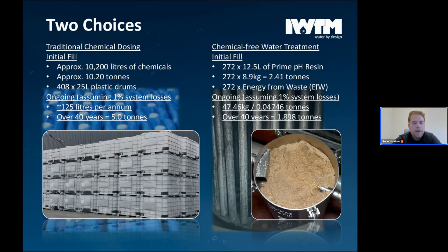And if you didn't know what chemical-free water treatment is, it maintains and protects closed-loop heating or cooling systems from corrosion damage without the use of chemical inhibitors or biocides to kill bacteria or any cleaning agents. And we do this by controlling the causal elements of corrosion rather than continually addressing the symptoms. And we used a German standard for water treatment called VDI 2035, which was released back in 2009, where if you were to meet the strict set of water parameters, you've engineered the water to be in a non-corrosive state.